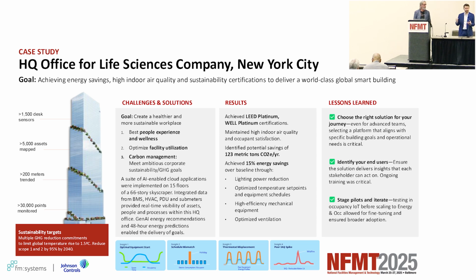Another example: we combined energy data with occupancy information and trended energy per capita, seeing how much energy was used per person. It was even, then all of a sudden we got a huge spike. So either we were using a ton of energy or nobody was in the space. Turns out nobody was there, because that day was a newly recognized corporate holiday, Juneteenth. The building was still running as if everybody was there, but nobody was in the space.